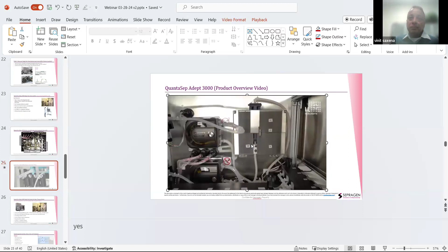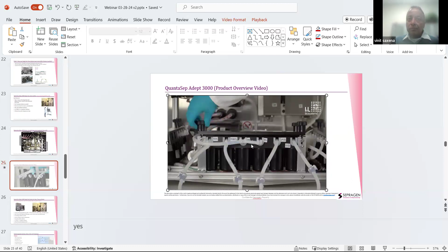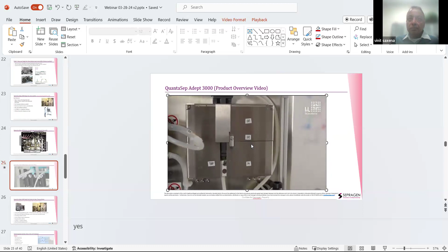Welcome to this introductory video about the unique QuantaSep single-use system. The SU features all the benefits of the traditional QuantaSep system, including some innovative design features that are optimized for even the most demanding production environments. The SU's core fluidics is a completely interchangeable sterile fluidic pathway. The flow path contains all the sensors required for a complete analysis and processing of your sample. The single-use sterile pathway completely eliminates the need for complex cleaning validation and can be exchanged in approximately 15 minutes. The flow path has a complete sensor suite that includes pressure, pH, temperature, and conductivity sensors, and features a twin wavelength UV cell that covers the 254 and 280 nanometer range.